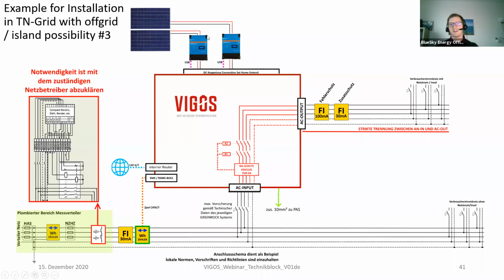these battery DC-DC chargers will start as soon as the PV panels get sun. And as soon as they start, they will charge up the battery to a specific point. And as soon as the batteries have reached their start voltage, you will get an AC out voltage again. This is what we call black start: starting without any additional grid.